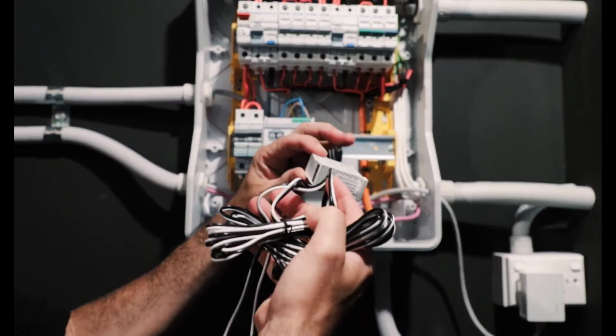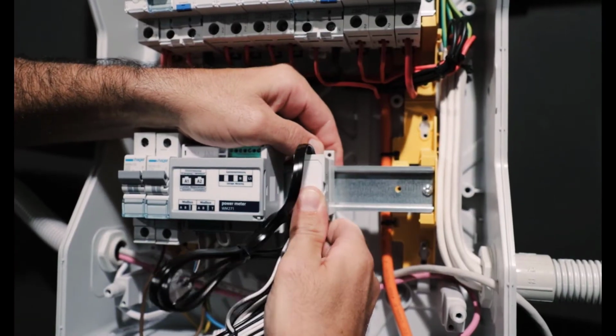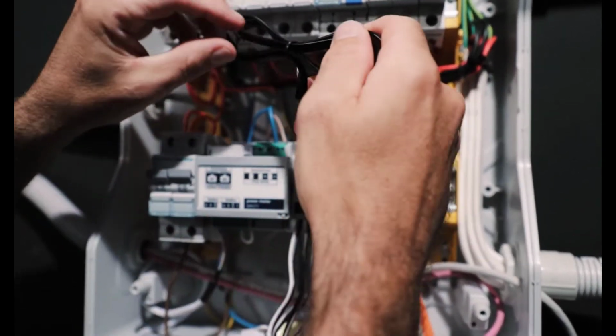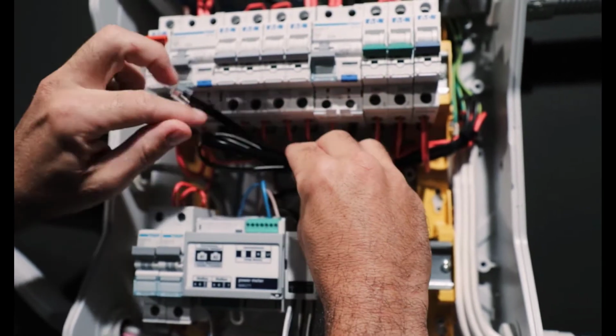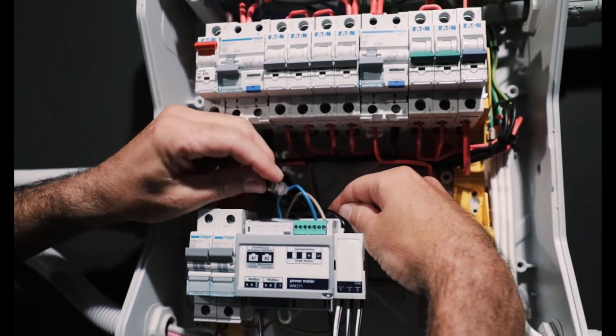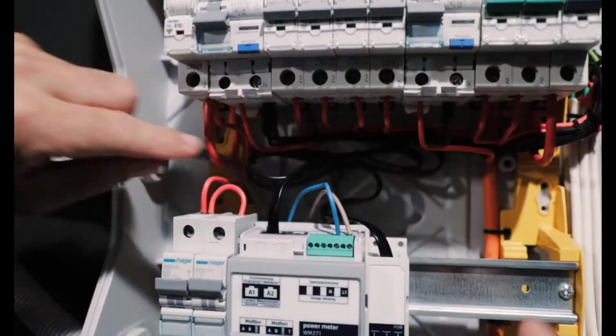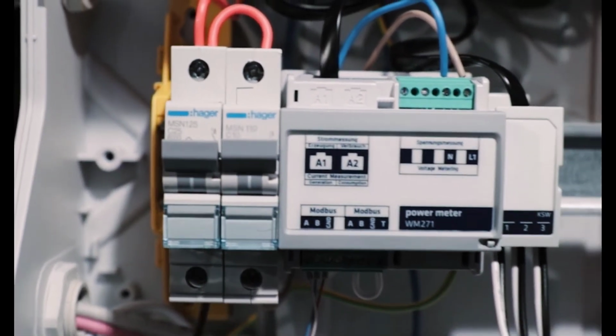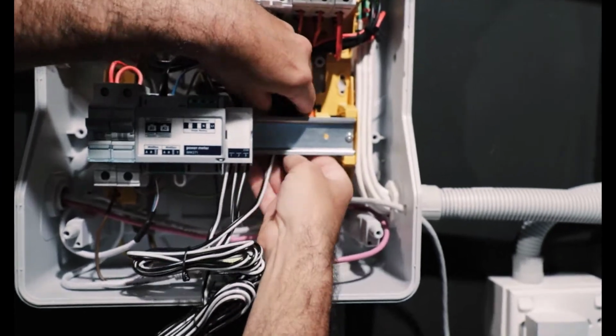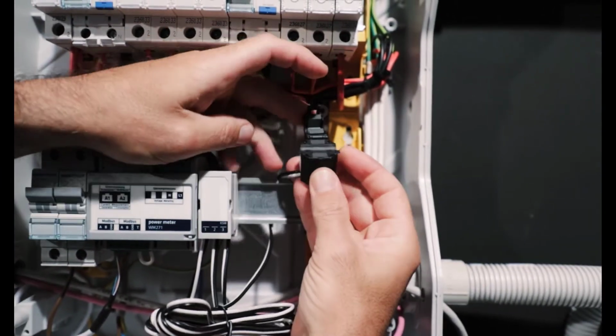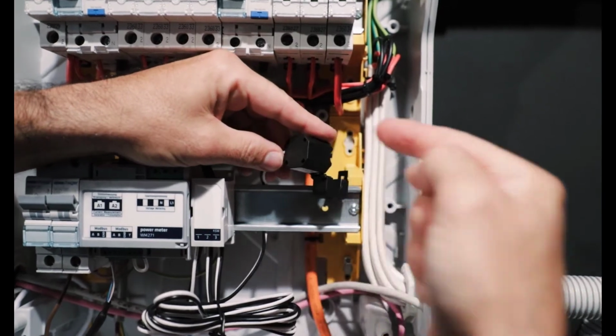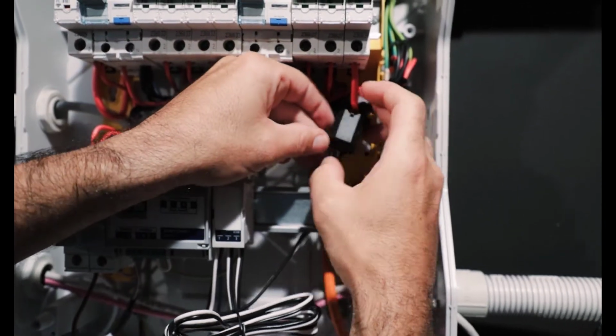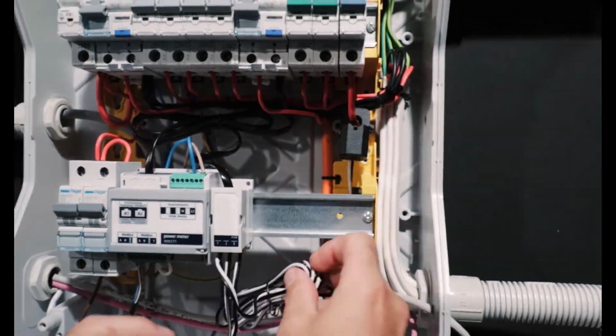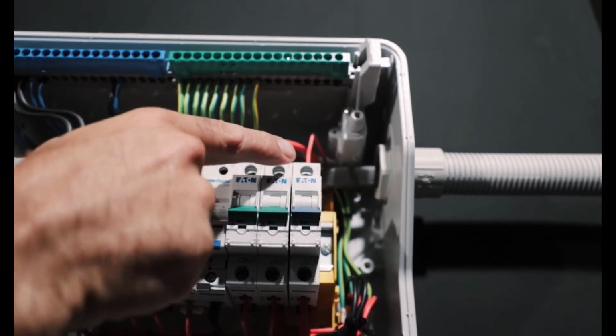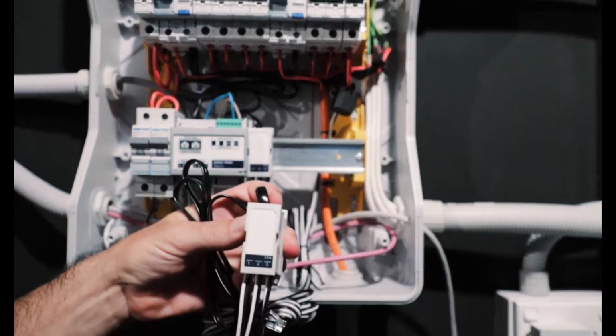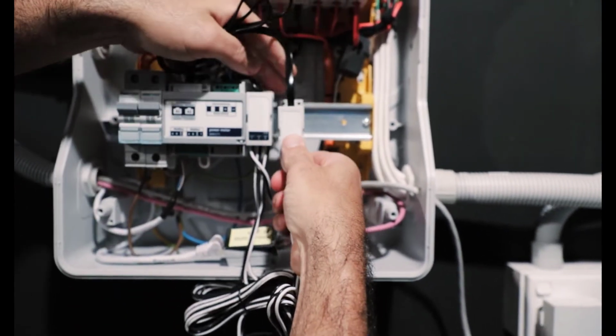And once more, we take our CT set, transducer on, we take this one into the A1 terminal, which is looking at generation. And very simply, take this onto the AC supply coming out of the MCB, which is connected to the solar input. So we have solar in to the MCB, and transducer number 2 is going to be for our CTs measuring consumption.